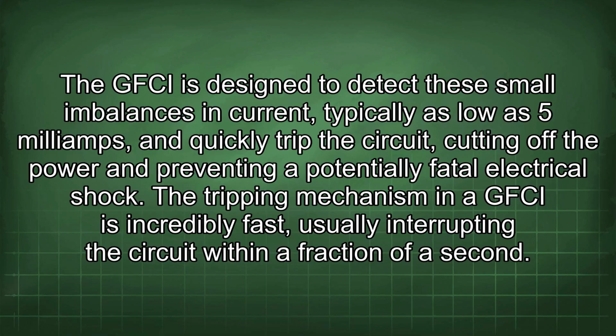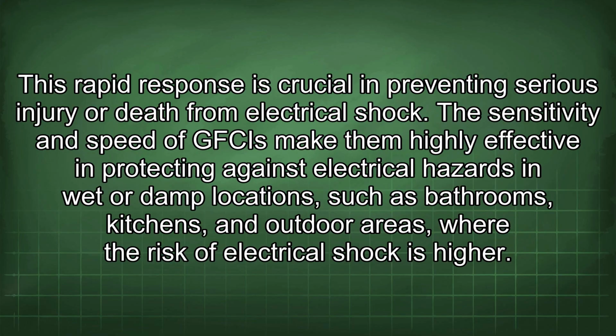The tripping mechanism in a GFCI is incredibly fast, usually interrupting the circuit within a fraction of a second. This rapid response is crucial in preventing serious injury or death from electrical shock. The sensitivity and speed of GFCIs make them highly effective in protecting against electrical hazards in wet or damp locations, such as bathrooms, kitchens, and outdoor areas where the risk of electrical shock is high.